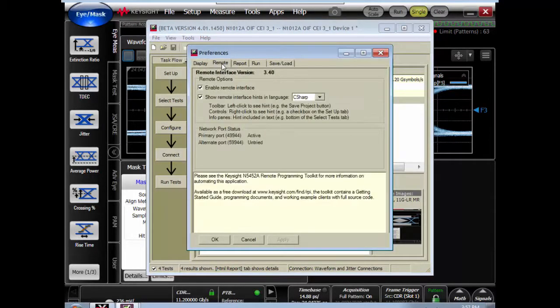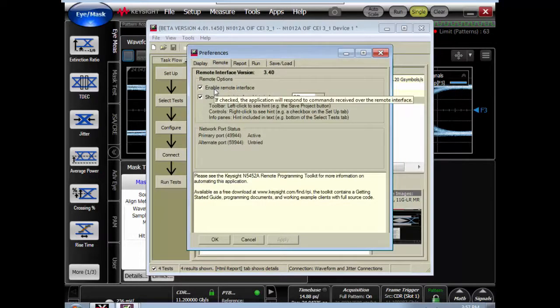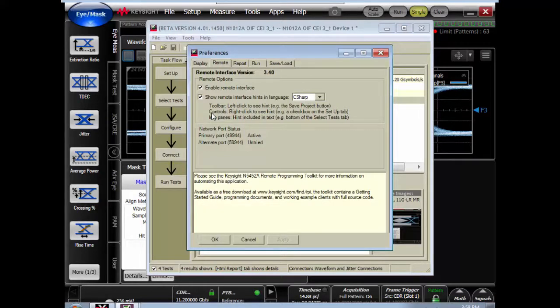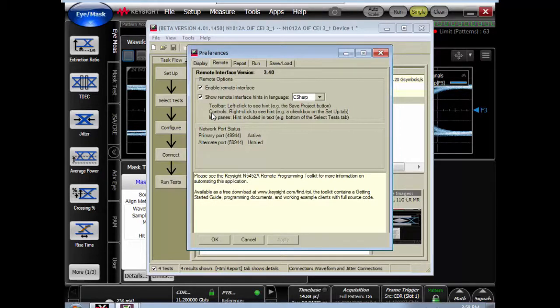Make sure on the remote tab that enable remote interface is checked, and we also want to make sure that the show remote interface hints are active as well. And this is an easy way to find out what the required methods and properties are to set and run in order to perform the compliance app automation.